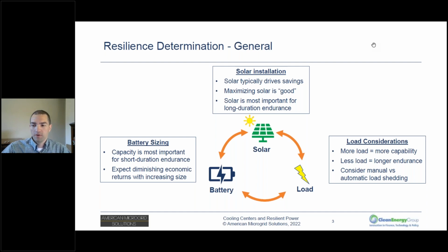So you start with the most solar and battery you can get, and here's what you need to do to your load: reduce it to half or a third of what you normally use to achieve your resilience goals. We approach the problem from both sides to come to a single configuration that meets the budget and performance constraints. The capacity of the battery tells you your worst case endurance, and the solar installation tells you how much better your typical result will be than that worst case.